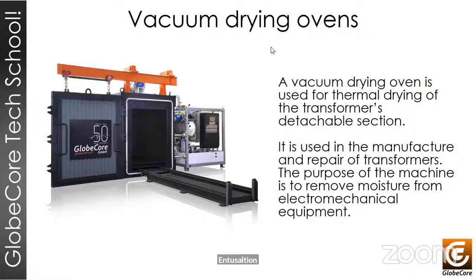The first objective to be achieved is certainly to impart the insulation with sufficient dielectric strength so it can withstand the required tests. Added to this is the intention to reduce the aging rate of insulation while operating, as well as to ensure the ability of the windings to withstand electrical and electrodynamic effects. Paper oil insulation in transformers is designed for reliable operation as long as it has high insulating properties, such as resistance, dielectric strength, electrical capacity, and low dielectric losses. These factors depend first and foremost on the humidity of insulation.